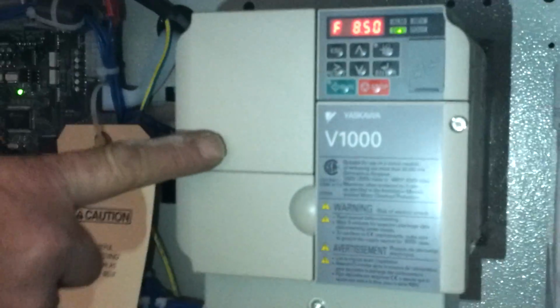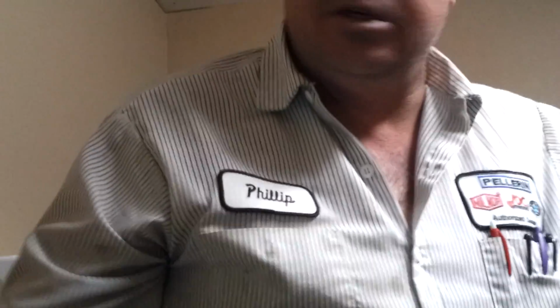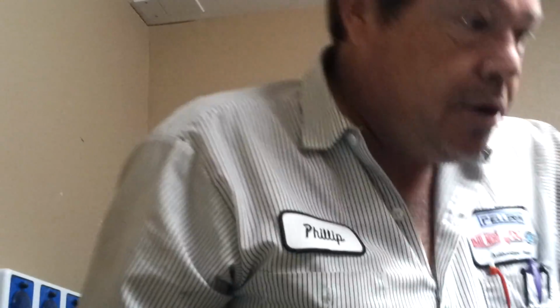Is this only for this model, or is it also for the 300G machine that's over there? Yes, same thing. Because they've got their doors closed. You want to leave those doors open because if not, you've always got power coming through this contactor, and you always have this inverter powered up, and you don't want to have voltage running through it at all times. Unnecessarily. Right, correct. Now your two large barrel fuses that I was saying, this is your transformer, this is your inverter and your motor.